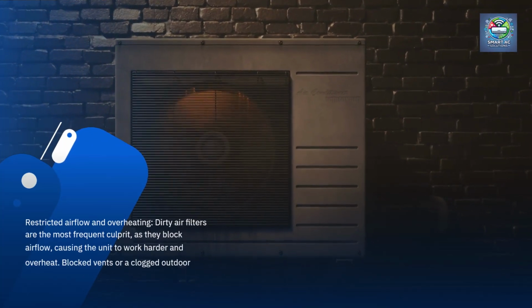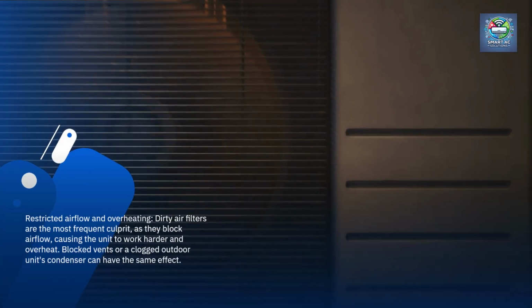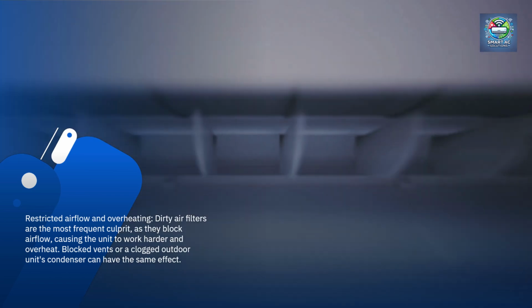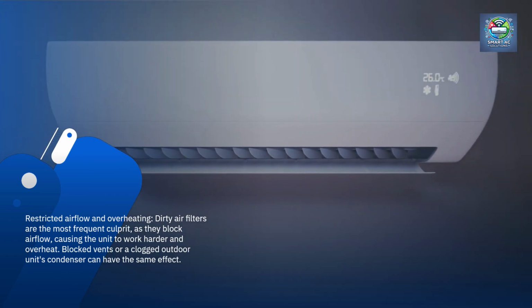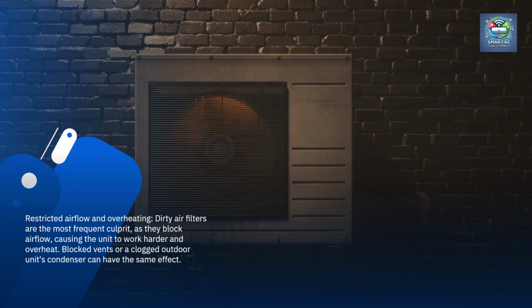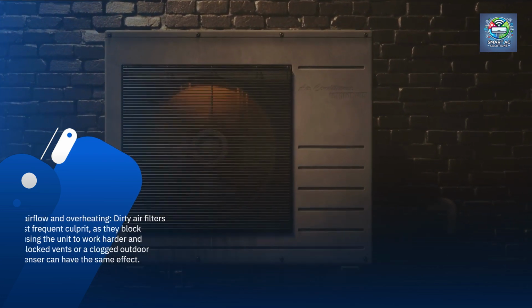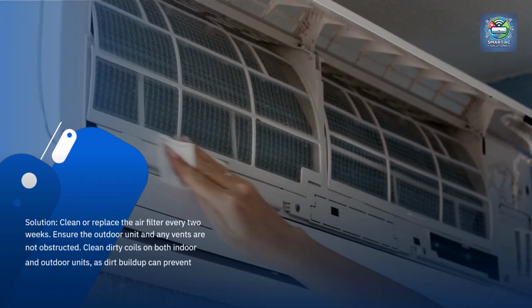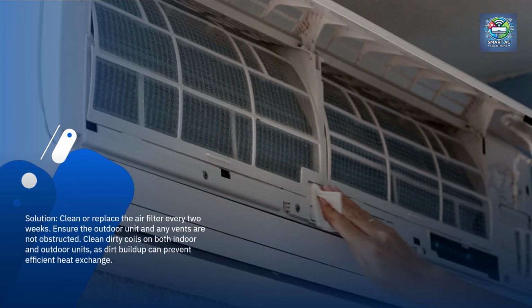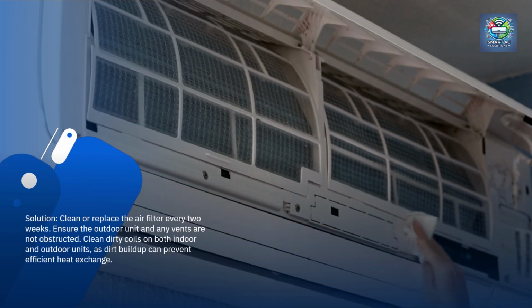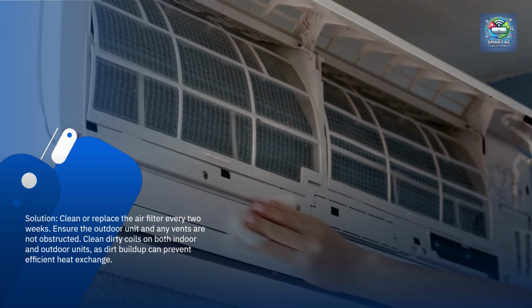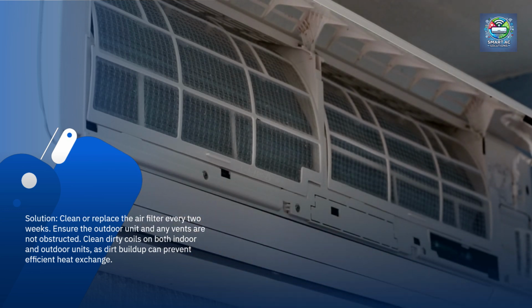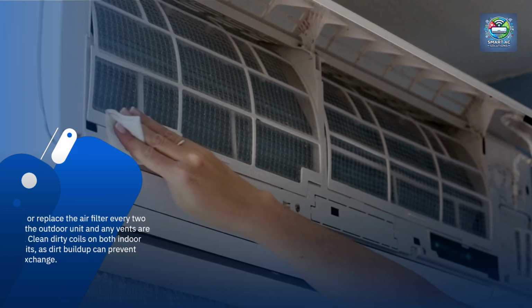Restricted airflow and overheating. Dirty air filters are the most frequent culprit, as they block airflow, causing the unit to work harder and overheat. Blocked vents or a clogged outdoor unit's condenser can have the same effect. Solution: clean or replace the air filter every 2 weeks. Ensure the outdoor unit and any vents are not obstructed. Clean dirty coils on both indoor and outdoor units, as dirt buildup can prevent efficient heat exchange.